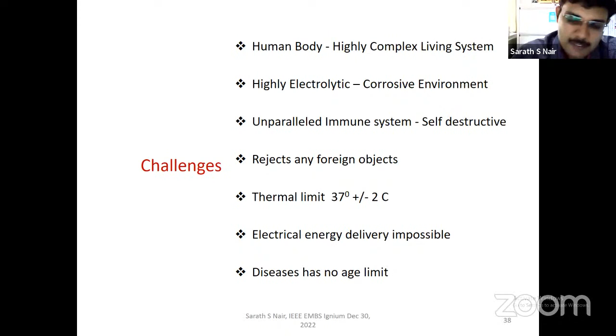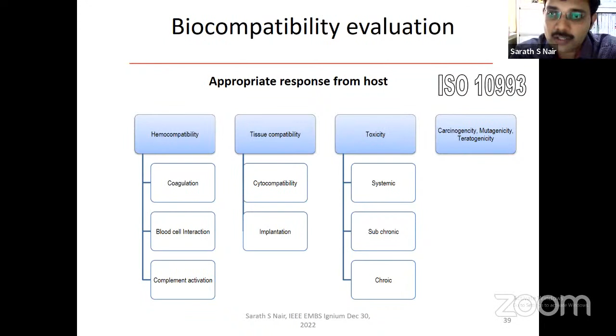So even if we have all these challenges, so many developments have happened, which have to go through so many types of evaluations, which contain biocompatibility evaluations. We need to see whether the device is compatible with the blood and tissue, whether it is causing any toxicity to the body, whether there are any heat-producing, thermal problems and all. And also so much safety testing has to be done. I would categorize the safety testing into 3 different regions: mechanical testing, electrical testing, and electromagnetic compatibility testing.